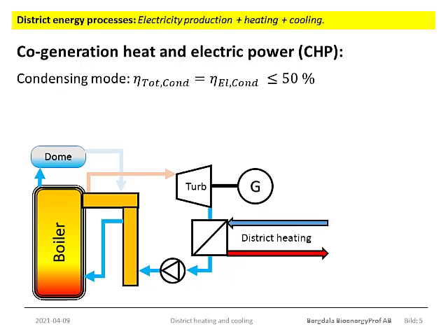So what happens when we introduce district heating is that we use the district heating water to cool the condenser after the turbine. But the return temperature from the district heating network will always be higher than the cooling water temperature we might use when using river water or cooling towers. Again, the tubing is, of course, more complicated than I show here, but what I try to illustrate is that you want to use the return temperature from the district heating system to set the temperature in the condenser after the turbine. And you want to do that to maximize the electricity efficiency.